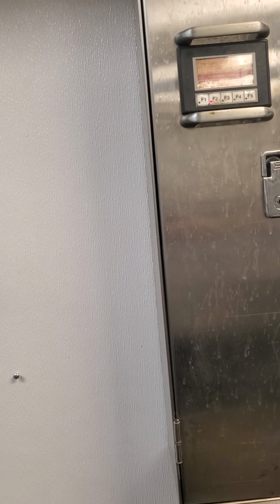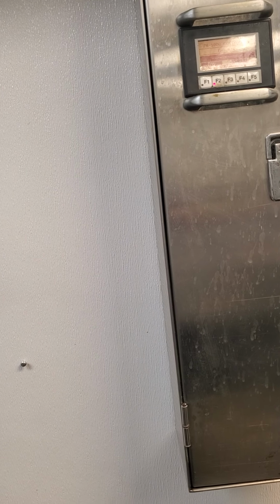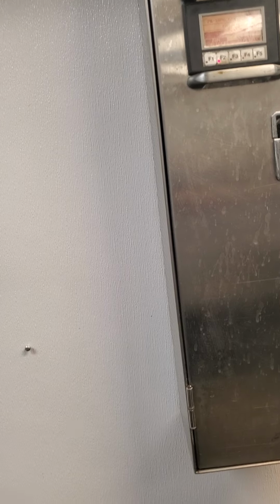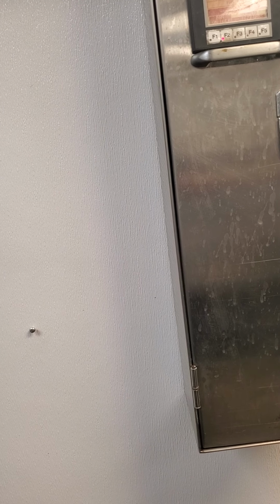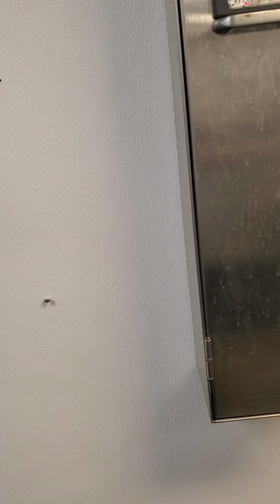They'll start getting smoke in here and they still won't get alarms. They were getting alarms like every other week in the beginning, and I just kept adjusting those pressure switches because I'd come out and the filters weren't dirty - it's just they have to go through so many banks of filters, it was tripping these. So believe me, the sensitivity, that's something I adjusted over the years.